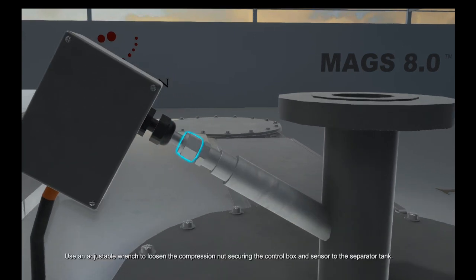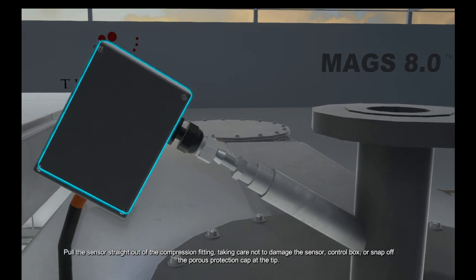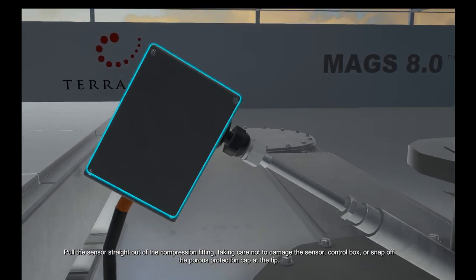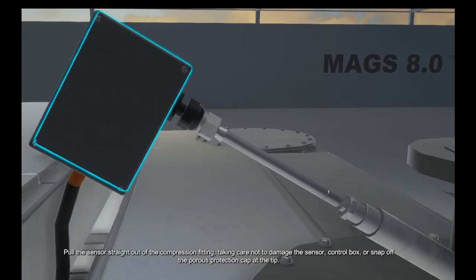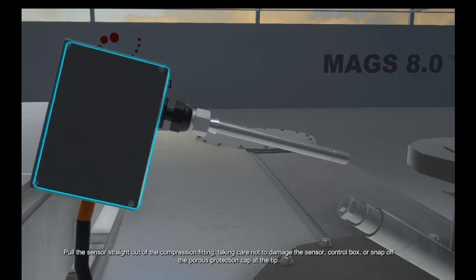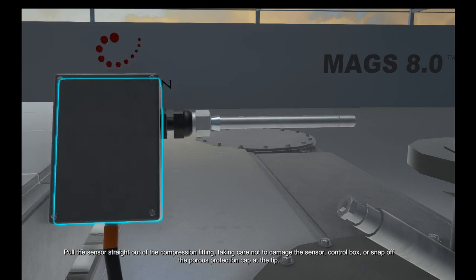Use an adjustable wrench to loosen the compression nut securing the control box and sensor to the separator tank. Pull the sensor straight out of the compression fitting, taking care not to damage the sensor, control box, or snap off the porous protection cap at the tip.